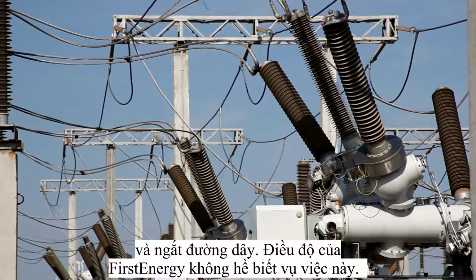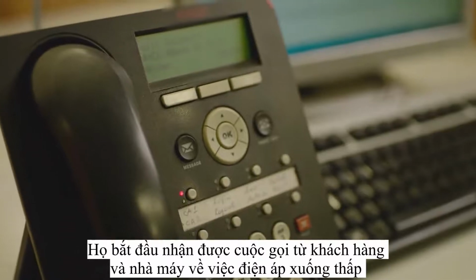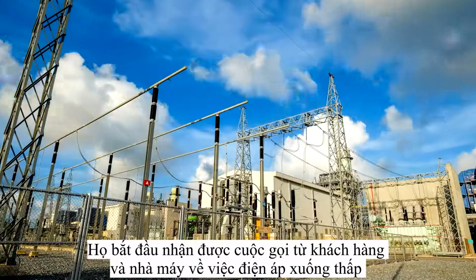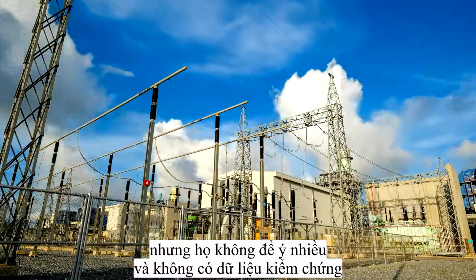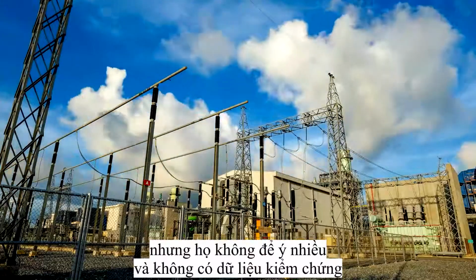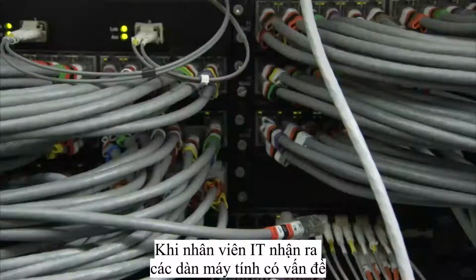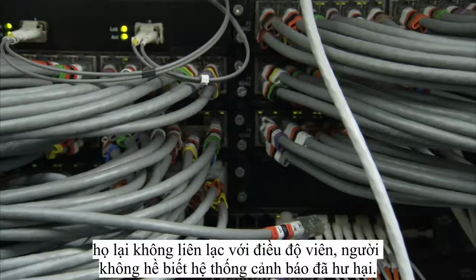Operators in the First Energy control room had no idea it happened. They started getting phone calls from customers and power plants saying voltages were low, but they discounted the information because it couldn't be corroborated on their end. By this time, their IT staff knew about the computer issues, but they hadn't communicated them to the operators, who had no clue their alarm system was down.